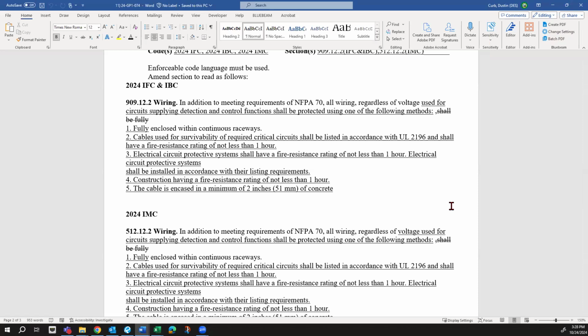I'm certainly not an expert in it, but I have run into this in several projects where the fire marshal was having difficulty getting that wiring protected, because NFPA 70 requires the protection and the building code is kind of silent on it. When you have protected shafts, they can run the wiring in those shafts. But in a pedestal building, when you're running horizontal over to the fire control room, that's outside of shafts, outside of horizontal protection. So I believe what they're trying to get here is to make it seen and obvious that that wiring does need to be protected by some means. Current code is kind of silent on that, or let's just say ambiguous.